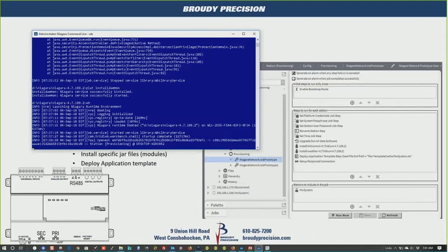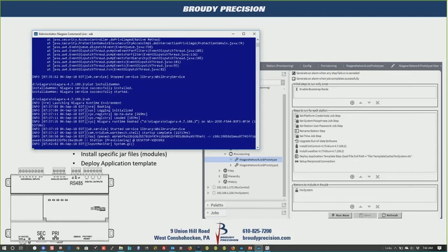One of the things on 4.6 to keep in mind, you cannot do your 600Es, your 700s, or your 300Es in 4.6 or above. So the highest those JACEs can go to is 4.4. And we'll never go any higher than that. And Honeywell 4.6 is on the Tech Center website. Right. And Tridium, there are Vicon. Vicons as well, yeah.